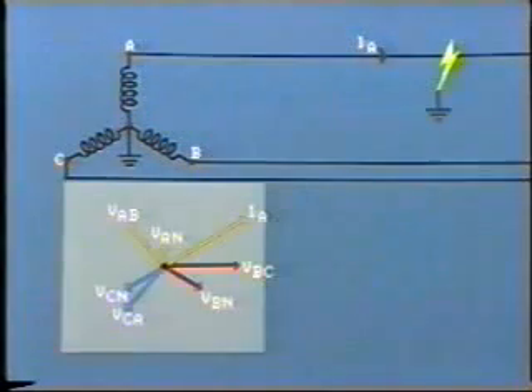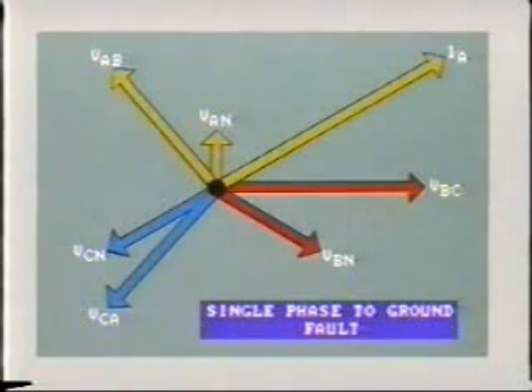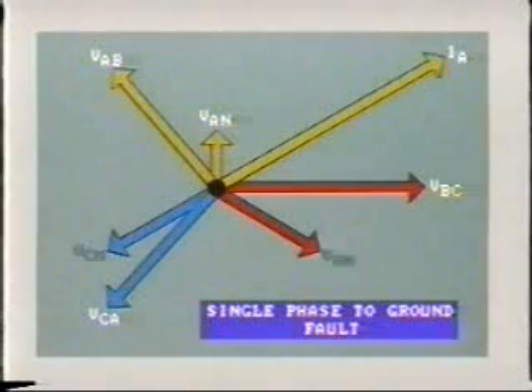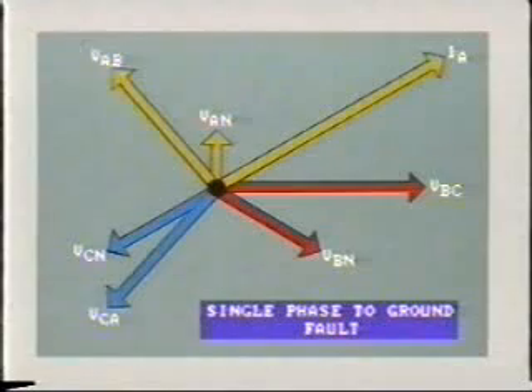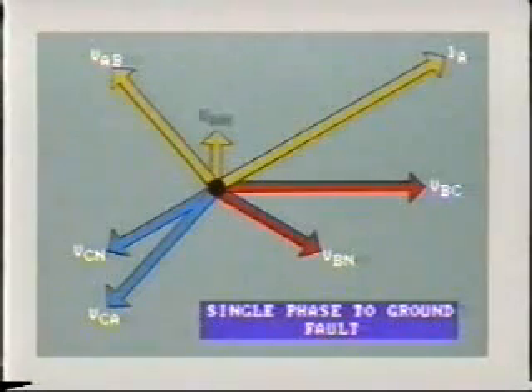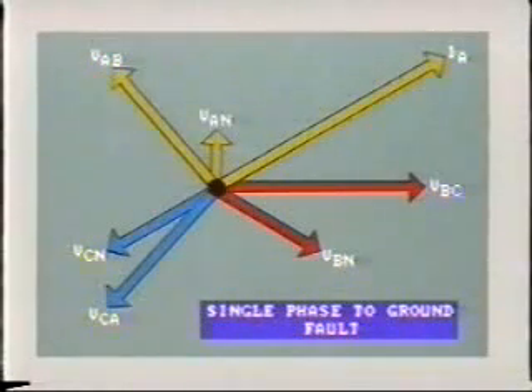Now here we see the conditions at the fault location for a ground fault on line A. The voltage between lines B and C remains normal, as do also the line B to ground and line C to ground. This is not so for line A to B and line C to A. In both cases, the voltage is reduced due to the fault on phase A. The voltage between line A and ground is drastically reduced. It could fall to zero if the fault impedance is zero, but usually ground faults do contain some resistance, and therefore a small voltage will remain.